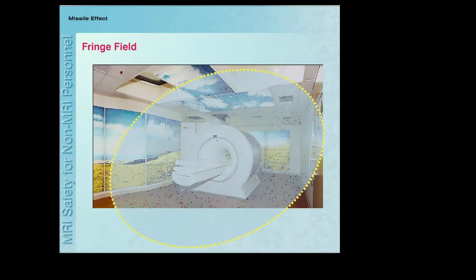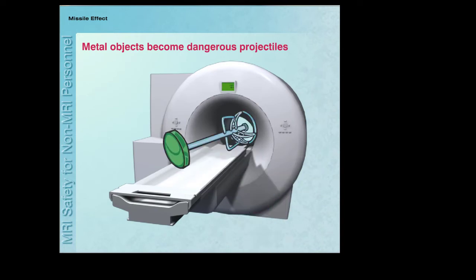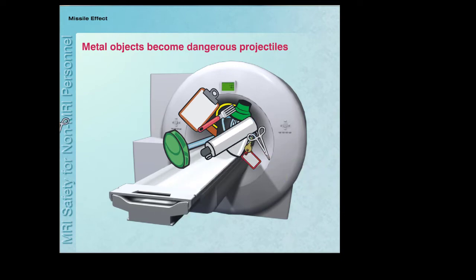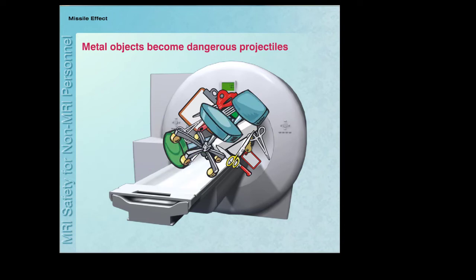The magnetic field extends out from the MR system in all directions, including above and below the scanner. This is often referred to as the fringe field. This figure shows a stylized depiction of the fringe field represented by the light-colored area. The powerful magnetic field of the scanner can attract certain metallic objects, causing them to move suddenly and with great force towards the center of the MRI system. This is referred to as the missile effect, as the attracted object becomes a projectile.